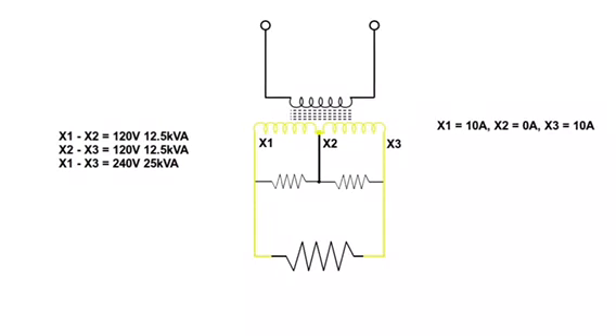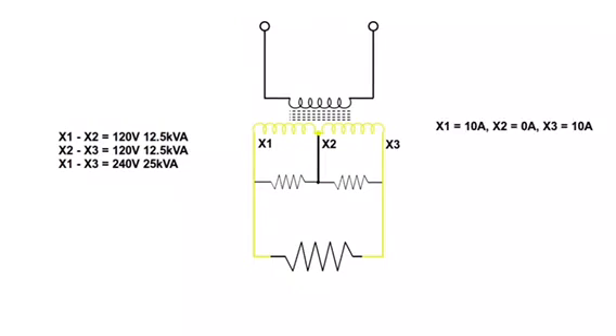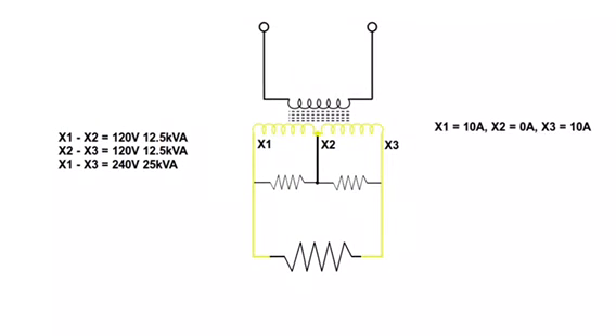So in this configuration, we could load the transformer up to a total of 25 kVA. At no point do you ever add X1 and X3 together for your total amperage. That's impossible. It's not how a transformer works. Each load is spread across a coil.